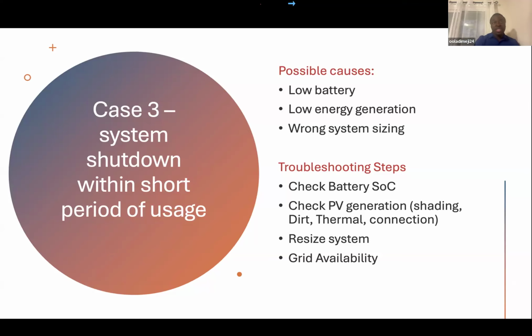Then what about the grid availability? Check. Because if you have built a hybrid system, which means that grid will be in support for you to have a particular expectation in terms of power delivery within some hours, then you want to be sure that you are getting it. If you've considered maybe 4 hours in the design, then you want to be sure that you are getting 4 hours from grid into the system every day.